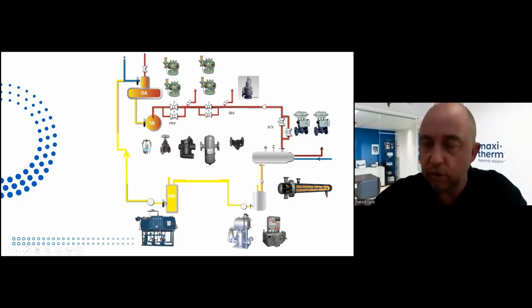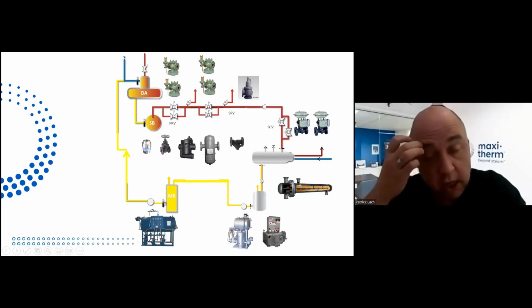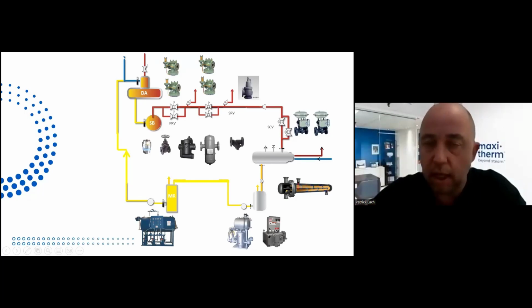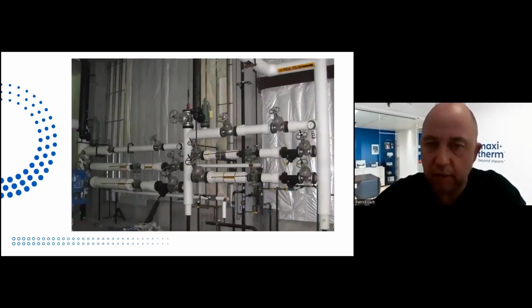Big steam noisy control valve, 1/3, 2/3, state-of-the-art, a dedicated condensate pump, steam or electric motor pump. Then we go back in the main receiver tank and you need all those pieces of equipment around the units, which, you know, a lot of leaks over the next 20 years and maintenance over the next 20 years. And this is a 2-stage PRV station, takes a lot of room, a lot of footprint. There's a cost for those ugly walls, a cost for fire protection, lighting, and everything else.